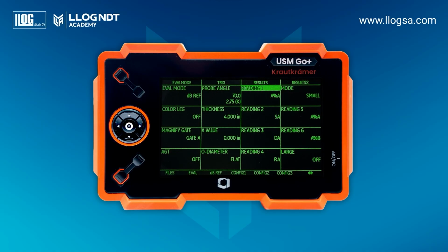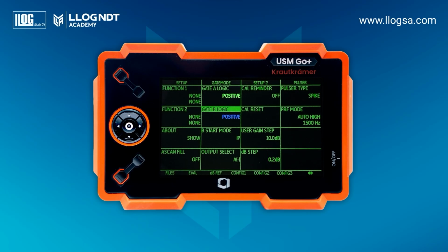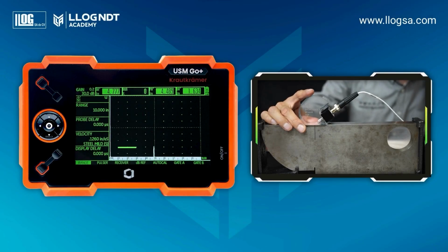We will use 4 measurement readings. Reading 1. Select SA, distance or path traveled. Reading 2. Select A, % of A, representing the echo amplitude that crosses gate A. Reading 3. Select PA, projection or surface distance. Reading 4. Select DA, gate depth, and deactivate the rest of the readings. Finally, deactivate gate B. The values of these and other functions will change according to the requirements of the test to be performed. After the previous adjustments, we are ready to perform angular beam standardization.